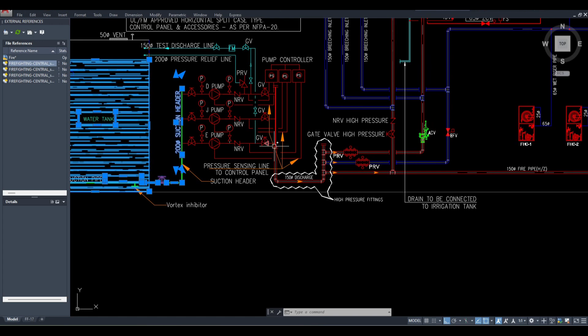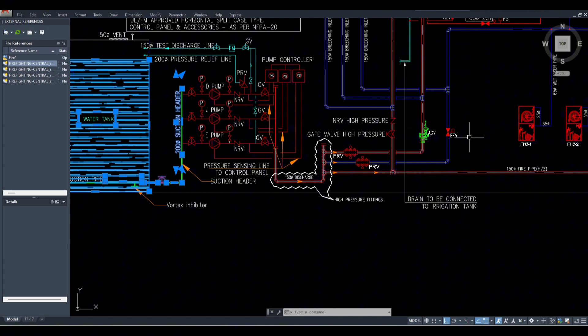Okay, so normally electrical pumps are powerful and big in size, so once it runs, it has a limited capacity and cannot deliver water below its minimum capacity. So for that purpose, to keep the pressure in the line always at an optimum or above a minimum level, let's say there are two scenarios. One scenario is 6.9, another is 10. Okay, so 10 bar or 6.9 bar, whatever your project design specifications are. So you have to always maintain that pressure. So whenever for any reason there is leakage or a break or any drain, whatever the reason, if the water is drained and the pressure is low, then this pump will be activated directly, and it will start delivering water into the system slowly and maintain the pressure in the line. Okay, which should not be less than 6.9 bar in any case.